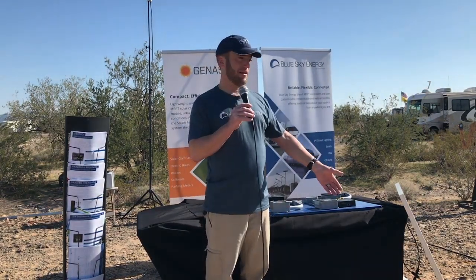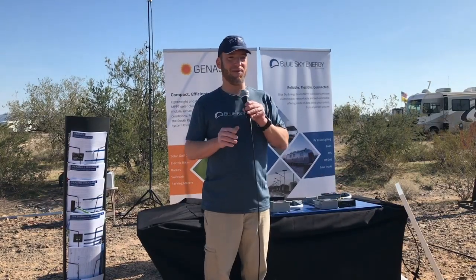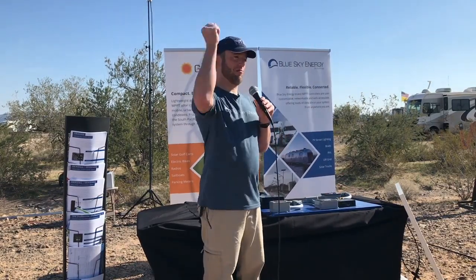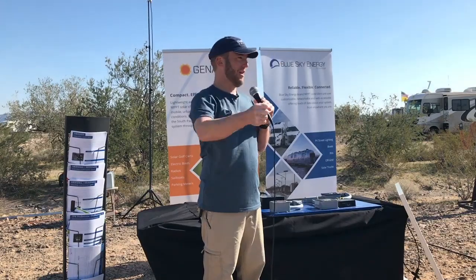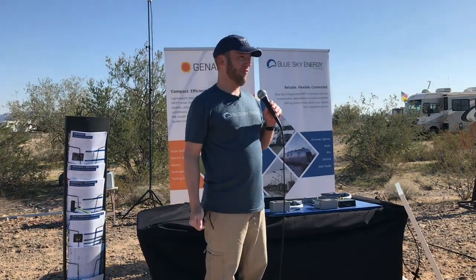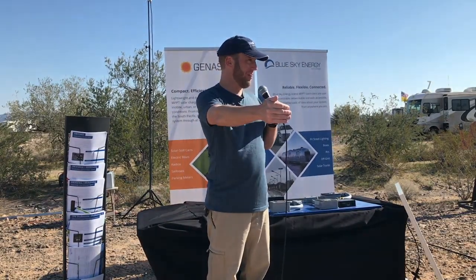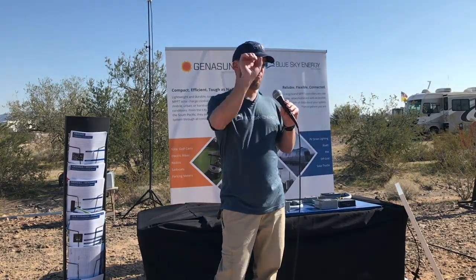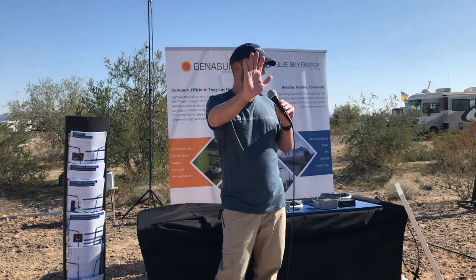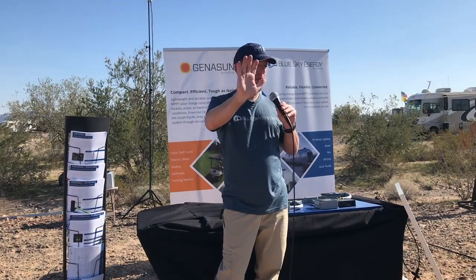You don't want to have your converter actively charging and disconnect the batteries, because if we think of it as a fire hose pouring water, and all of a sudden you take the batteries away, that water has no place to go. I don't care how fast you are on that nozzle, that water is going to splash against your hand a little bit, and that splash ends up being a voltage spike or load dump.